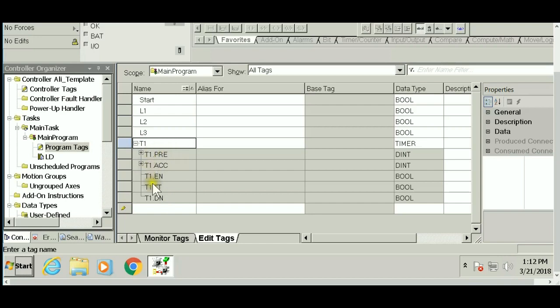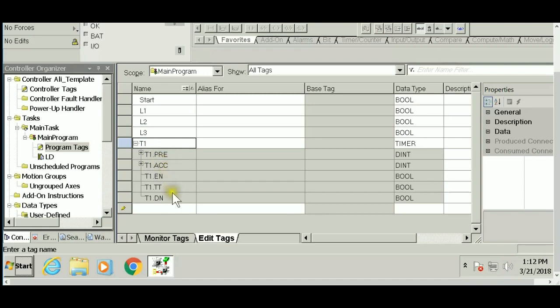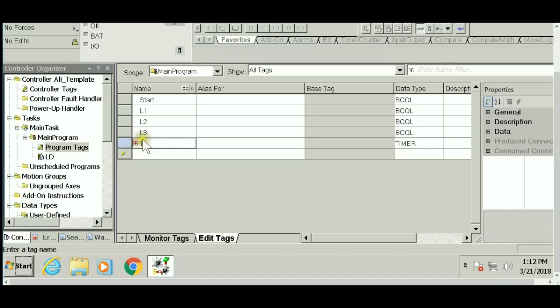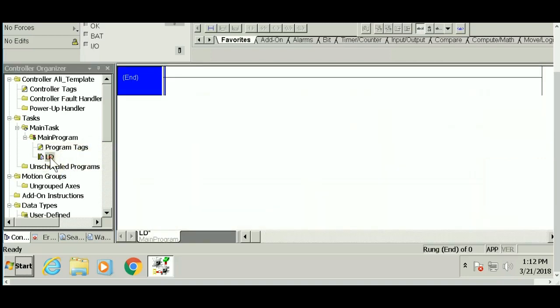You'll see preset, accumulator, enable bit, timer timing, and done bit displayed in the program tags. This is how the program recognizes them. The syntax is timer name dot parameter: T1.PRE for preset, T1.ACC for accumulator, and so forth.